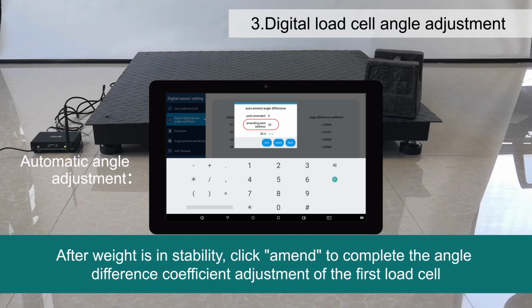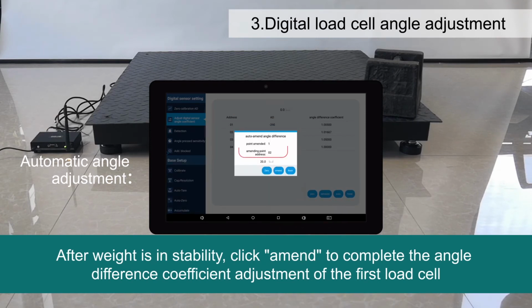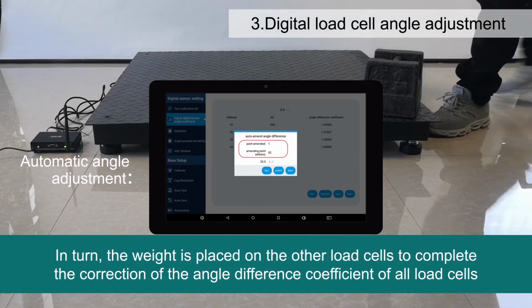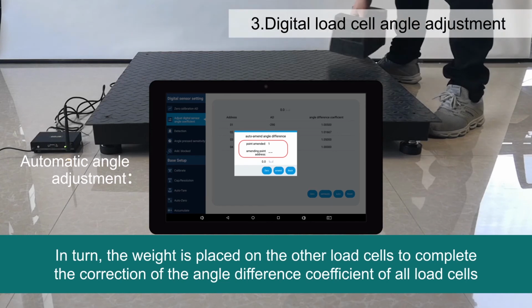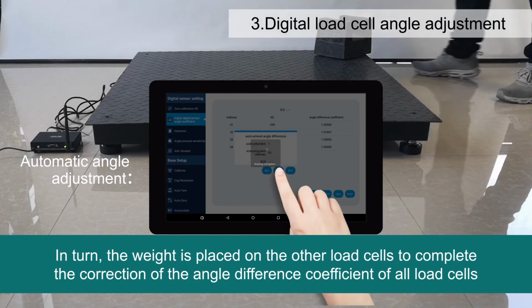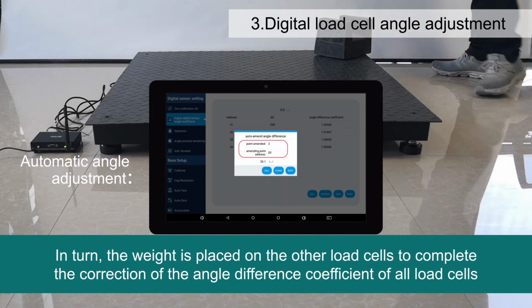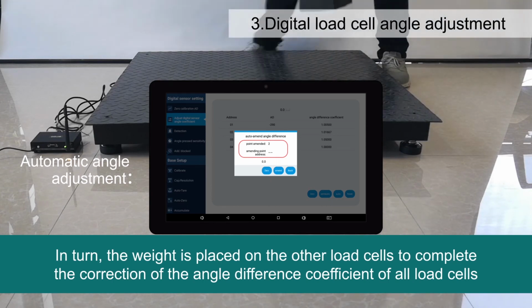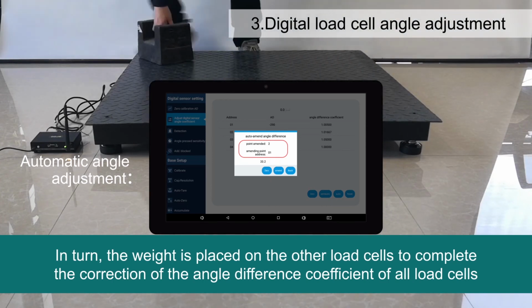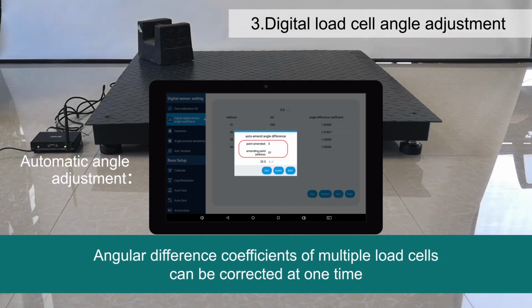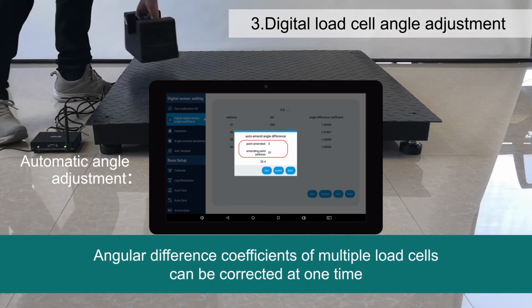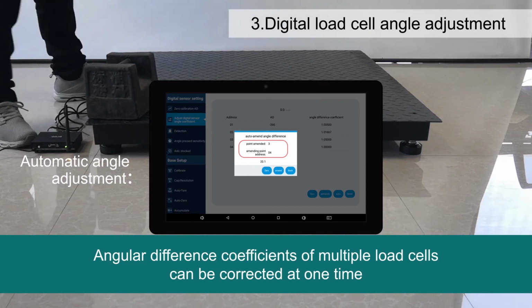After the weight is stable, click Amend to complete the angle difference coefficient adjustment of the first load cell. In turn, the weight is placed on the other load cells to complete the correction of the angle difference coefficient of all load cells. Angular difference coefficients of multiple load cells can be corrected at one time.